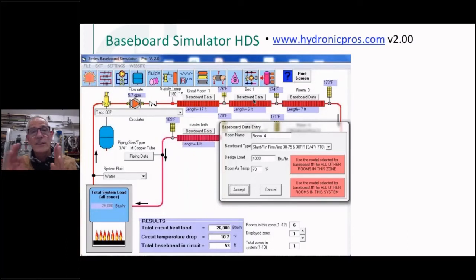And you can see that the length of the fin tube starts to get longer and longer as I go around the circuit because my temperature is dropping. Even though I had the same BTU per hour load in every room, every time I go through a heat emitter, I drop some temperature. So instead of using the supply water temperature to size baseboard or using the average water temperature, if I said, well, if I start with 180 and I come back at 170, you know, my average temperature through the emitters, and size it by that, this is going to get it even a little bit more accurately because it's going to size every baseboard to the exact load in that room at the temperature that it's receiving as it goes through there.